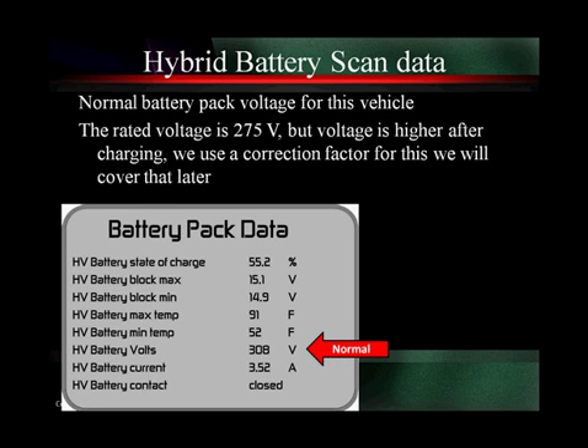So our temperatures look normal, and we come to our next thing, battery voltage: 308 volts. Well, if we go back and look at theory, this is where Doc Knoll and I get hyper sometimes — we don't like theory. The rating from the manufacturer of this battery is 275 volts, but we know the voltage is higher after charging. We use a correction factor for this, and we're going to cover it in a few minutes.